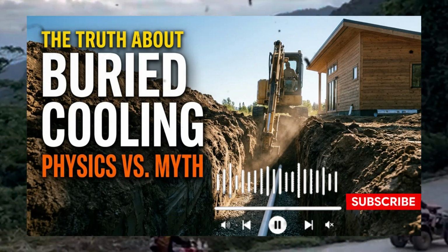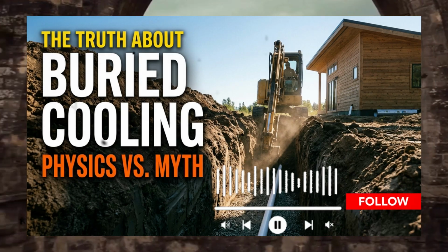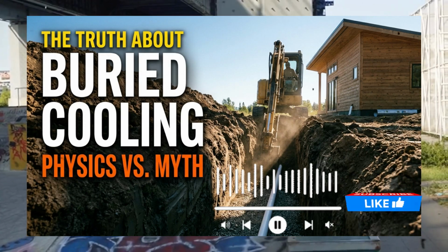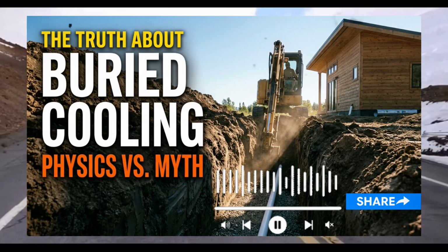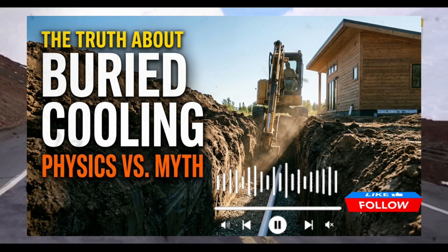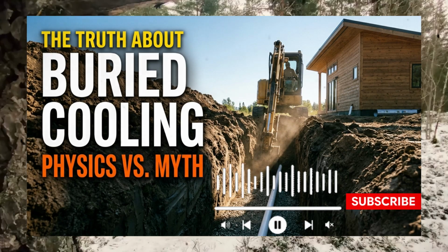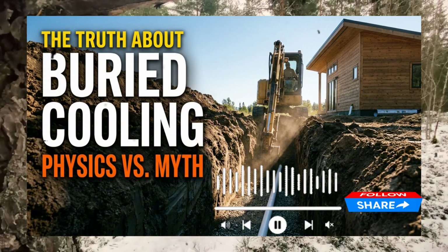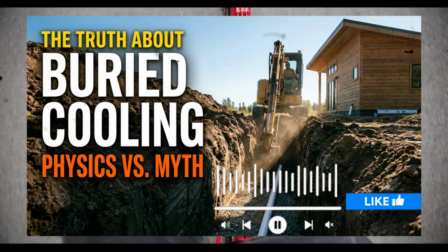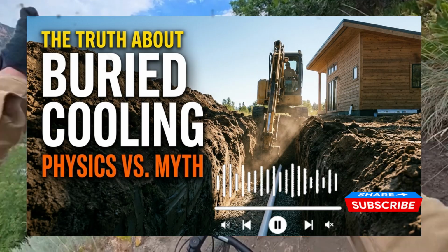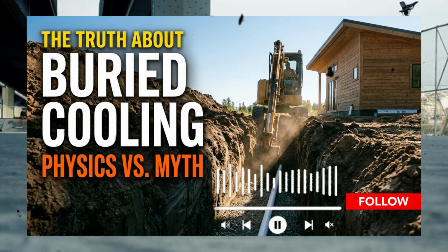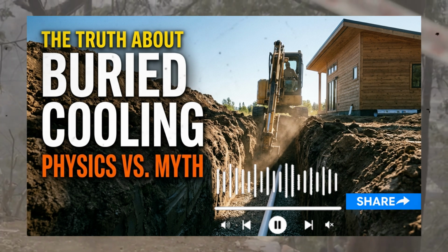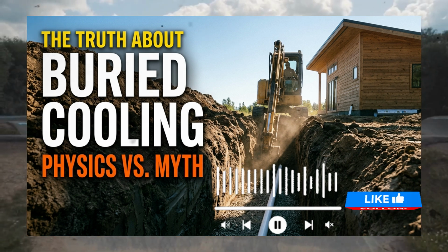During our midsummer trials, we mounted digital temperature and humidity sensors at 3 critical points: the outdoor air intake, the lowest point of the subterranean pipe near the condensation sump, and the indoor registers where the air is discharged into the cabin. On the hottest afternoon of the trial, when the outdoor ambient temperature peaked at 96 degrees Fahrenheit with 60% relative humidity, the thermal transition inside the pipe was stark.